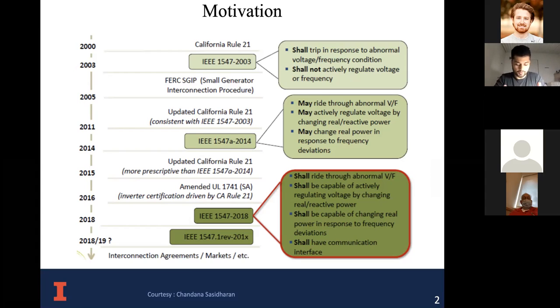But then as the years went by, DR increased, and then you need a revision in the standards. So in 2014, IEEE 1547 came up and went from shall to may. So you may ride through abnormal voltages and frequencies, you might have to ride through and maybe sustain, you may actively regulate voltage by changing real and reactive power, and you may change real power in response to frequency deviations. But then the penetration increased so much that in 2018 it was just a requirement. So you have to ride through, you have to be capable of actively regulating the voltage by changing real and reactive power. So it was just a must, a shall requirement, where you went from shall not to may to shall. And the reason being the increased DR penetration.